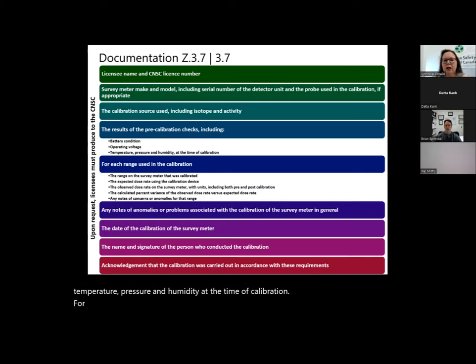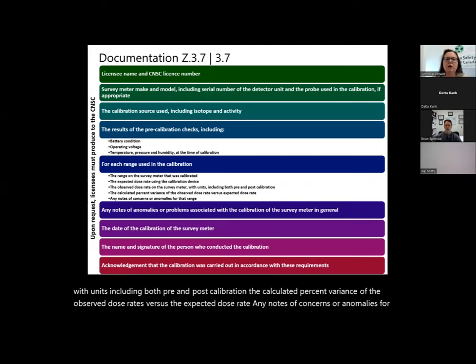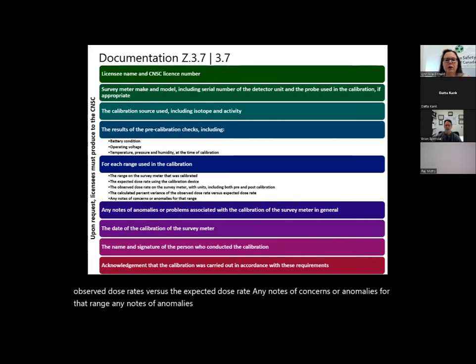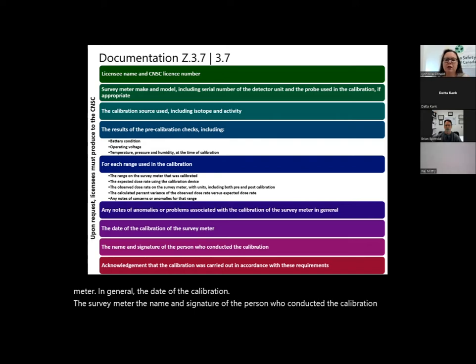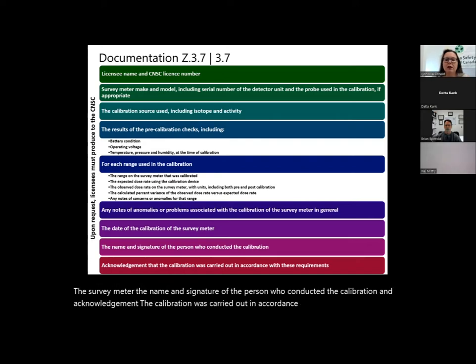For each range used in the calibration: the range on the survey meter that was calibrated, the expected dose rate using the calibration device, the observed dose rate on the survey meter with units, including both pre- and post-calibration, the calculated percent variance of the observed dose rates versus the expected dose rate, any notes of concerns or anomalies for that range, any notes of anomalies or problems associated with the calibration of the survey meter in general, the date of the calibration of the survey meter, the name and signature of the person who conducted the calibration, and acknowledgement that the calibration was carried out in accordance with these requirements.